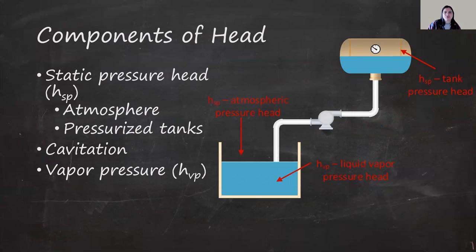Another type of head loss which may affect your system includes changes in pressure. The fluid vapor pressure, atmospheric pressure, and the use of pressurized containers become important factors in determining head. While not covered in detail for this presentation, I have included some factors which may help you determine if they're an issue for your system design. The pressure above the surface of the liquid will exert a force, which can either help or hinder the pump performance depending upon the location. There's less force when the atmospheric pressure is lower, such as at higher elevations, and more force when pressurized tanks are utilized.